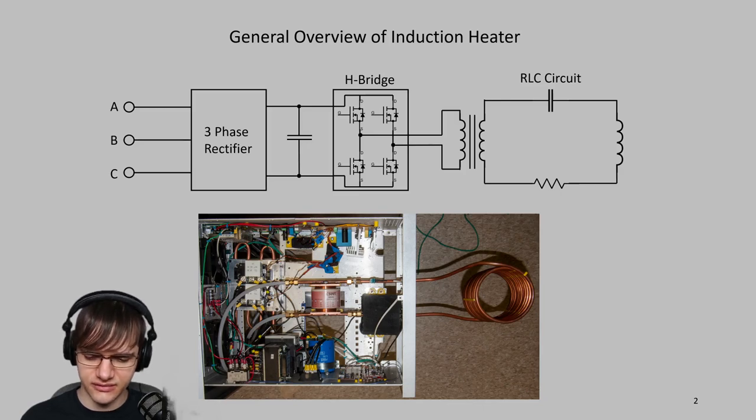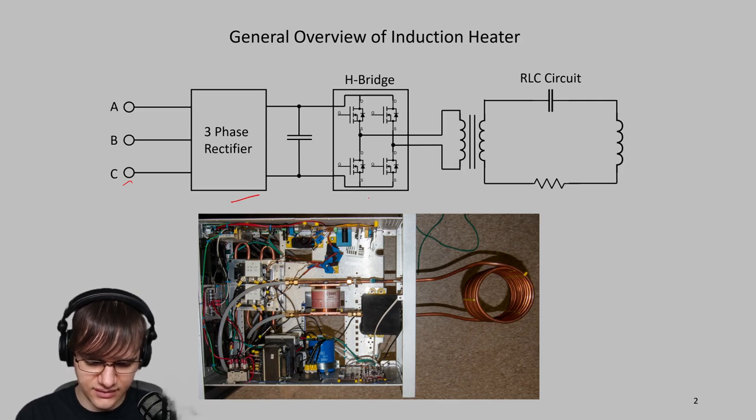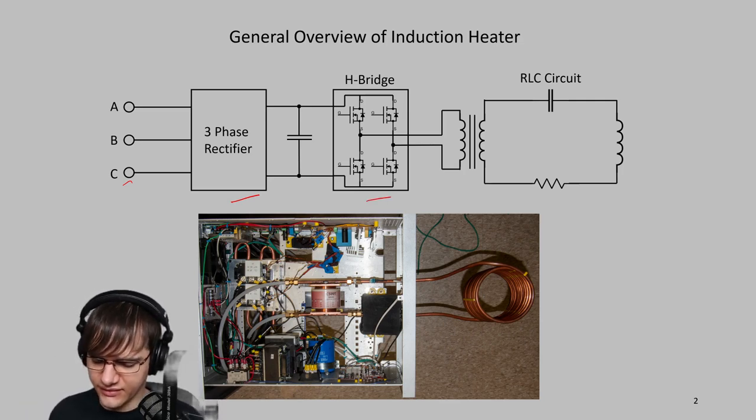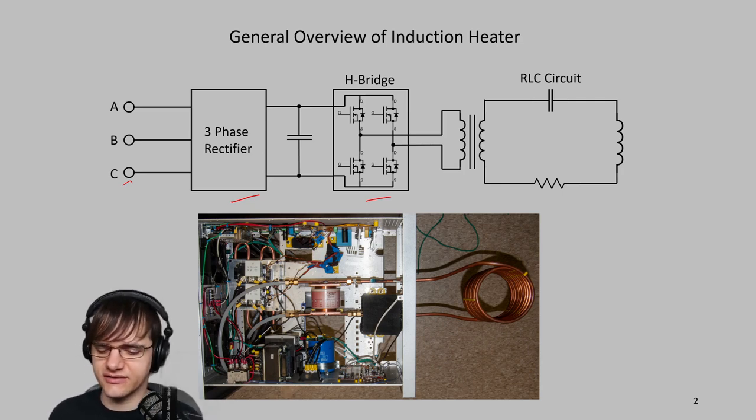For a general overview of what an induction heater is, you have a three-phase input, you rectify it to DC, and then you invert that DC back into AC again at a higher frequency than the line frequency. And you want to have this circuit in resonance because you get the maximum power transfer to your workpiece.